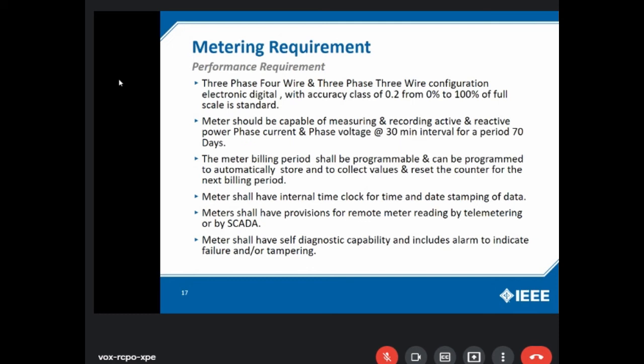Meter billing period shall be programmable and can be programmed to automatically store and collect the value and reset the counter for the next billing period. Billing period as per the NEPRA standard is 30 days. Meter shall have internal time clock for time and date stamping of data. All these are the performance requirements of the meter. Meter shall have provisions for remote meter reading by telemetry or SCADA. Meters shall have self-diagnostic capability and include alarm to indicate failures or tampering as well.